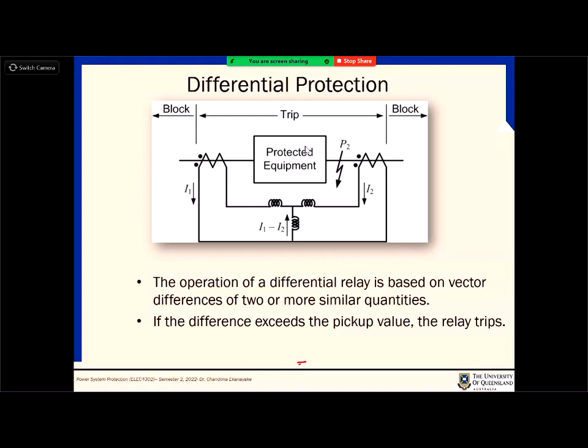Okay, so you have two wires, one coming in and the other side probably going out, right? As an example, in a generator, one side is connected to the neutral, the other side is probably connected to the phase. And then you measure the phases and the neutral. So if it is Y connected, then the addition of the three phases should be equal to what? Neutral. If it is not, then there should be some sort of current leakage in between those two. So very easy to do that. So you call that sort of protection scheme a differential protection scheme.